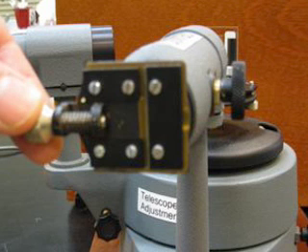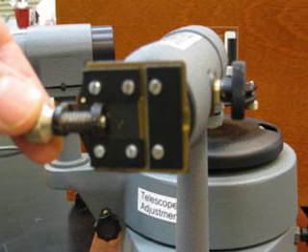The adjustment varies for different models. The goal of this adjustment is to get a thin sliver of light into the collimator. You want it to be as thin as possible without becoming too faint to see.